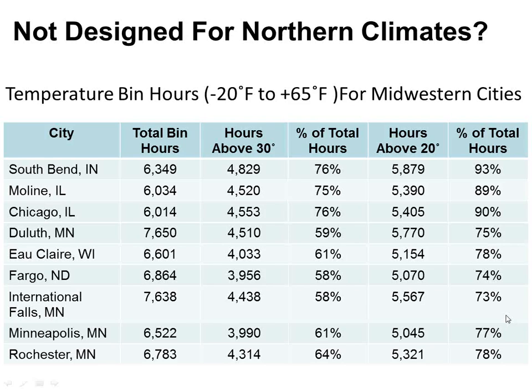The other thing is if you look at the bin hours, right? So there's 8,760 hours in a year. If I look at all of those hours, how many hours fall into which bucket, right? So if I'm looking only at heating hours, which means I'm looking at 65 degrees outside and less, if I look at those number of hours, in South Bend, I have 6,349 hours where I'm quote-unquote in the heating mode. In Chicago, it's 6,014, right? So basically 6,000 and a little change is what I'm talking about.